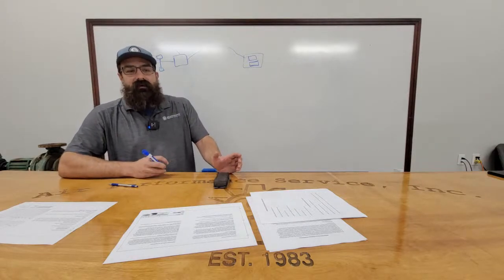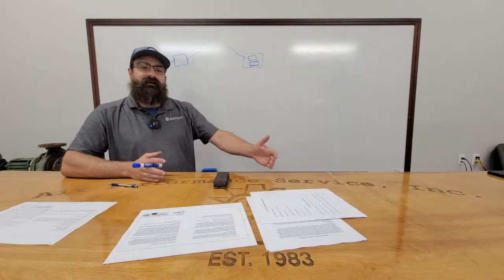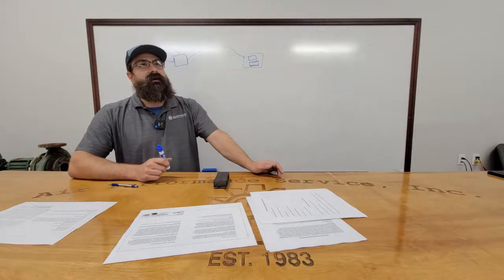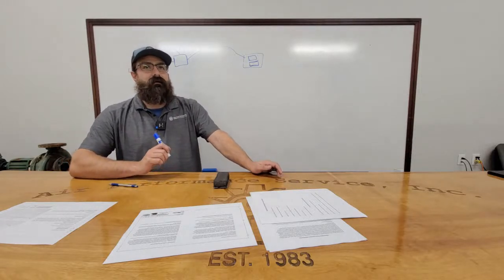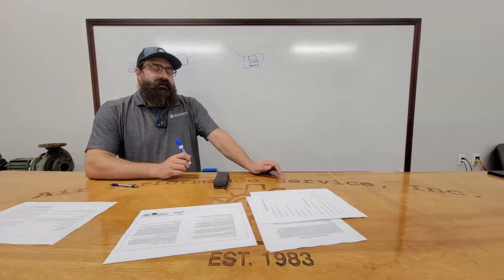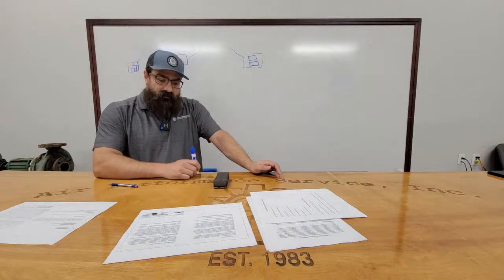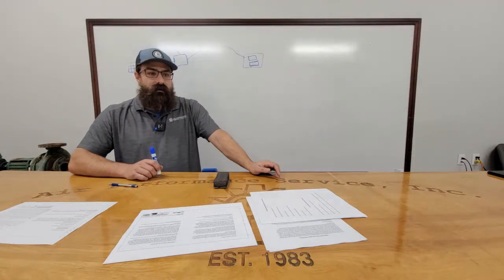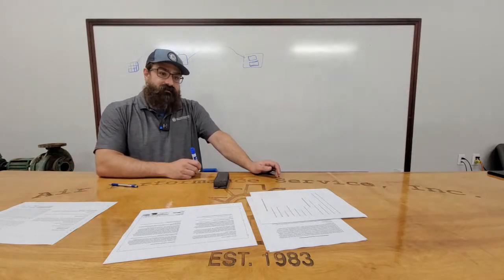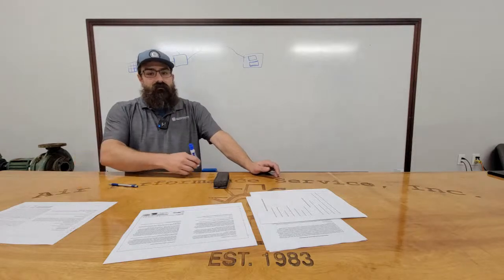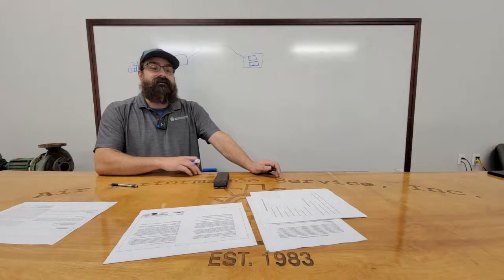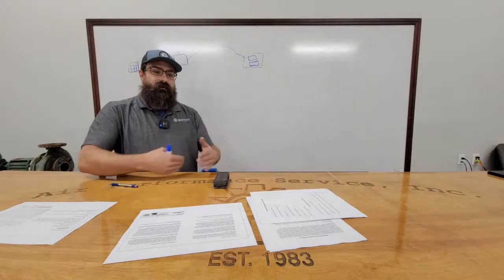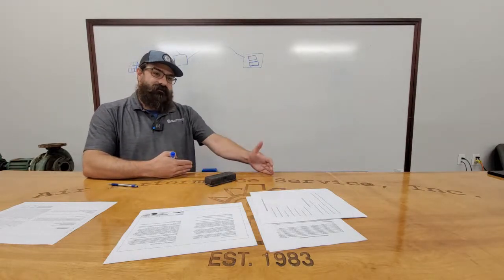You're just doing a different little bit of logic, right? One, you're looking at the terminal load of the box, one, you're looking at the space temperatures. The difference in using a space temperature function is that, if we're using temperature only, you can't guarantee that every box is going to be requesting cooling. Whereas if you use the load and you get to a load percentage, then you know your boxes are truly in a load, regardless of their set point. If somebody has changed an unoccupied set point, it's still in a load. It knows what its load is versus you having to guess what its load is just based on temperature.